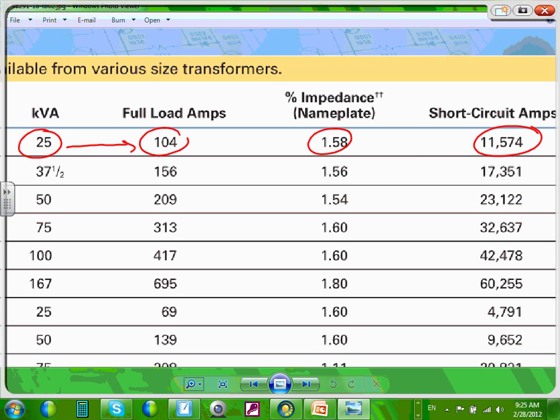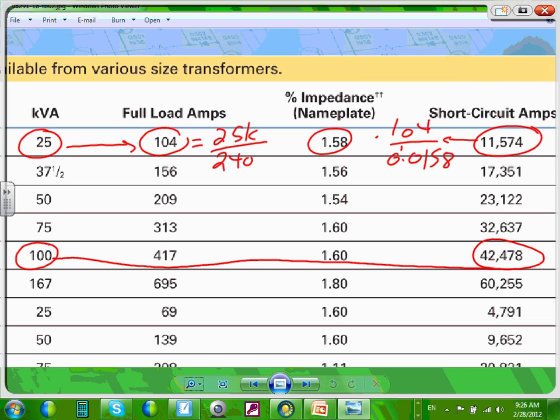And oh, by the way, this is not rocket science. You know what they're doing here? Here's how you find this one. You take the 25K divided by 240. That's how you find this. And then for this one, you take 104 divided by this impedance, 0.0158. And that's how you get these values. They might multiply it by 0.92. So the manufacturers of the transformers, guys, give you, here's a 100 kVA transformer, and here's all the information, the short circuit.